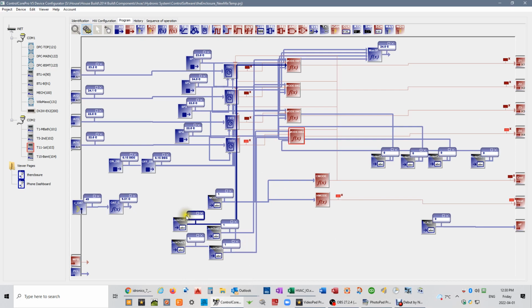And the lockout I created was for the ability to do testing, because this was automatically turning stuff on and off based on the set point, and I wanted to do some testing. For instance, when I had miswired the actuators, I wanted to turn one actuator on at a time, regardless of what the set point was. So I added these variable blocks that were 0 and 1, and they would allow me to set, like right now everything's set to true.